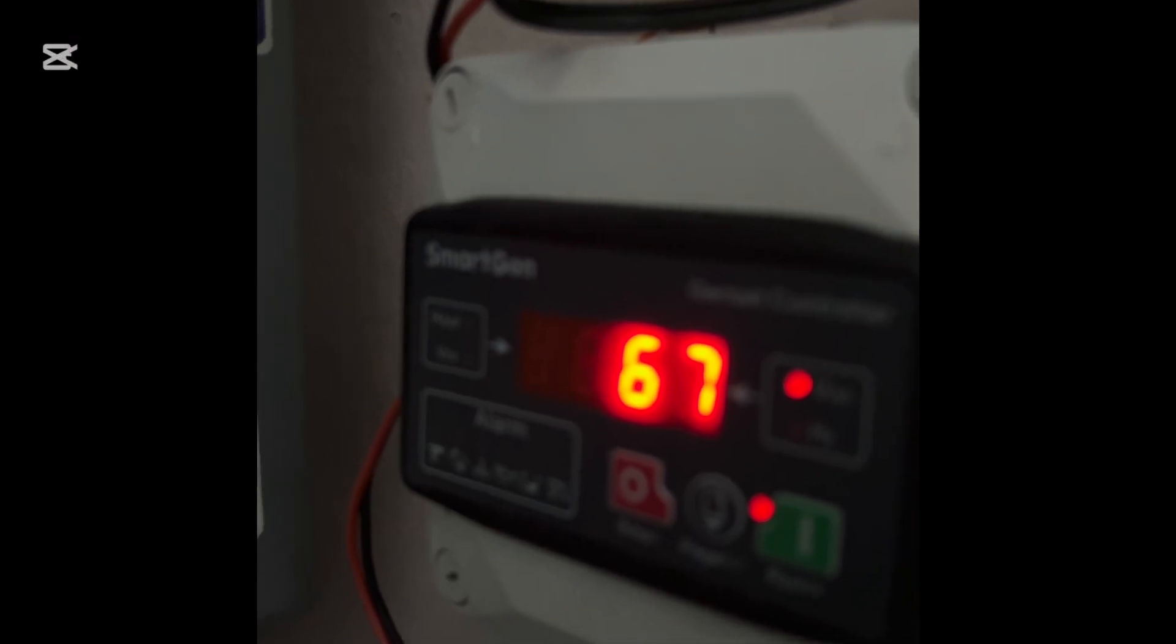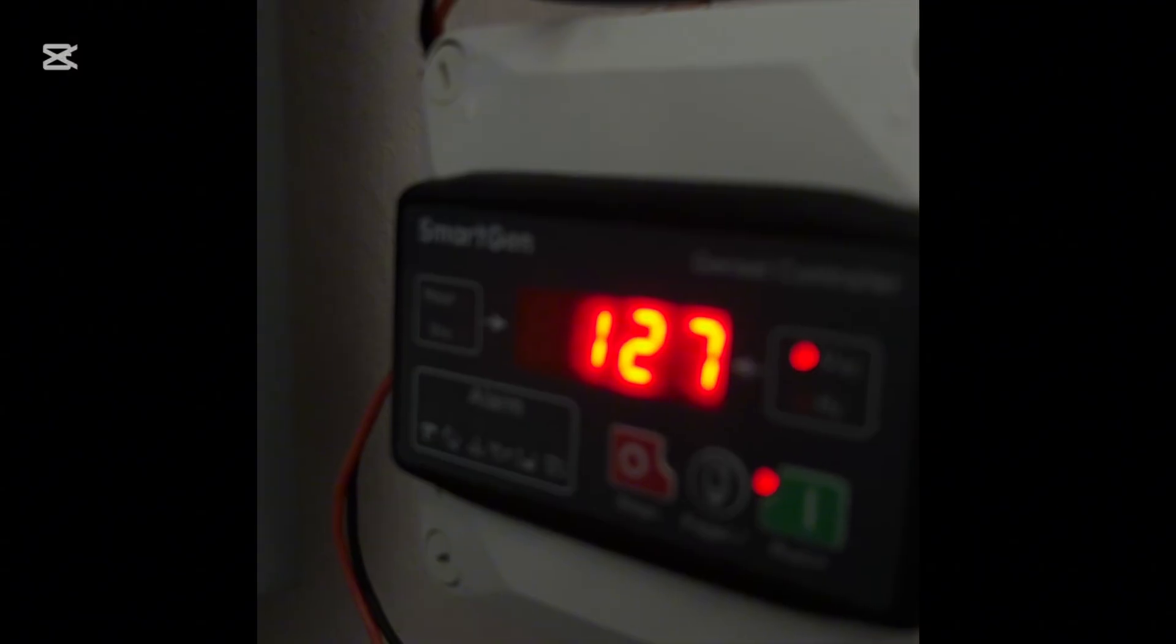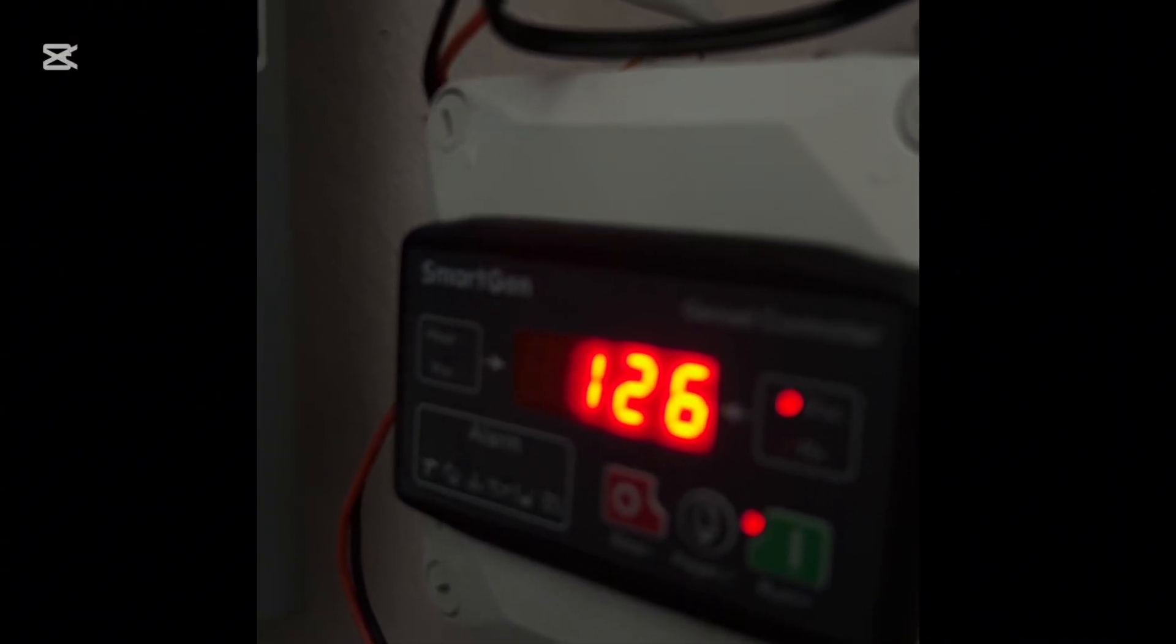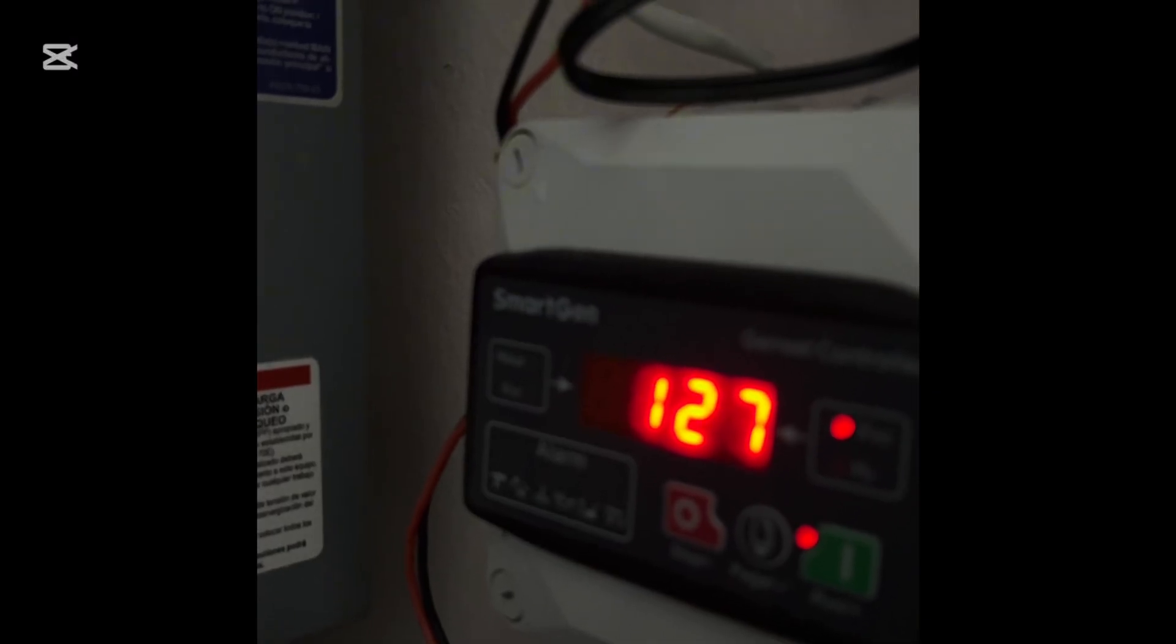You have the signal. Now the generator controller is going through its startup procedure which waits two seconds, then sends the signal to the starter. Here the generator is kicked in and after three seconds it disconnects the starter. Now we have voltage, so we have 126 volts coming from the generator and everything is working as you can see on my inverter here.